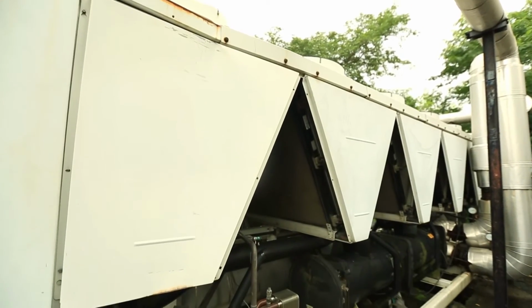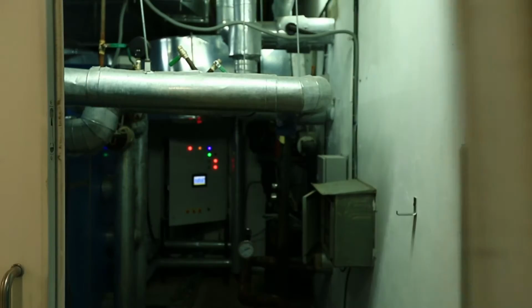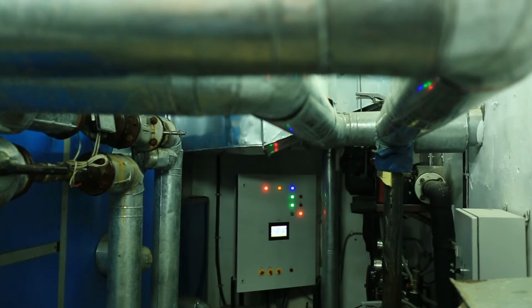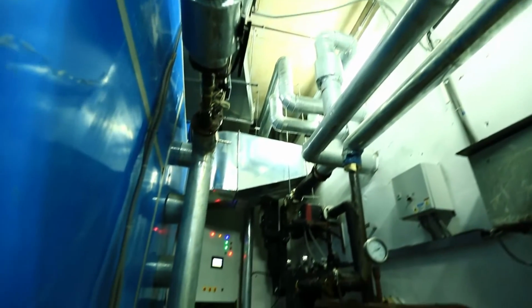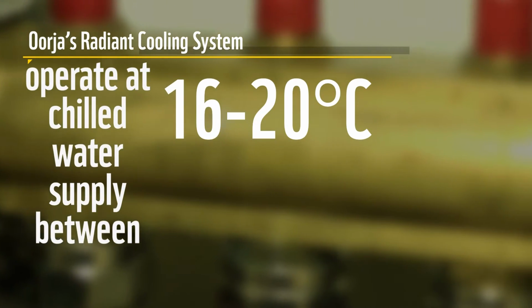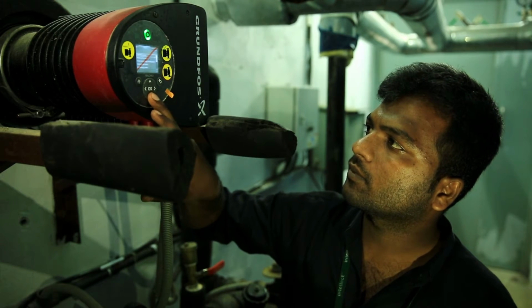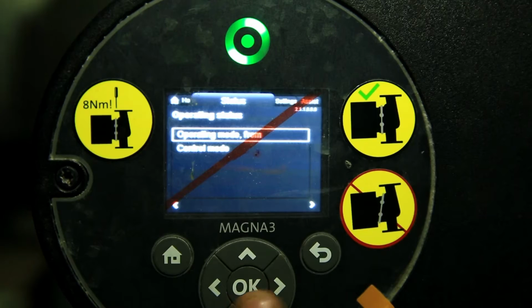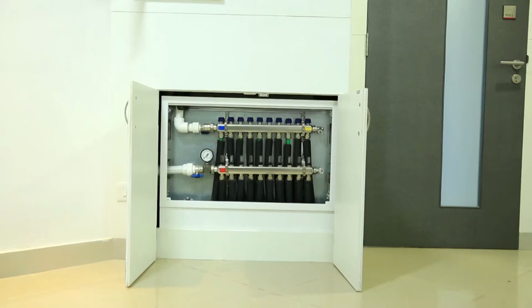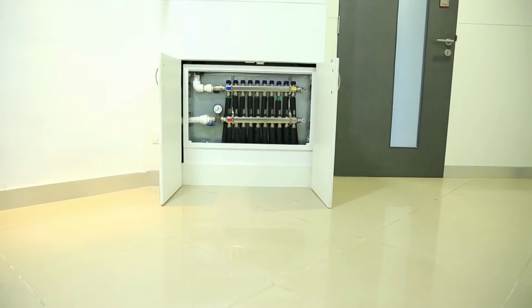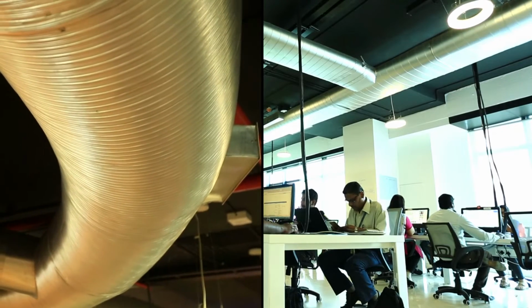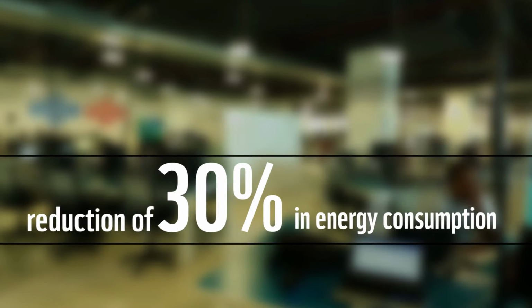Conventional centralized HVAC systems using chillers and AHUs require chilled water supply at 7 degrees Celsius, as compared to Oorja's radiant cooling system that can operate at chilled water supply between 16 to 20 degrees Celsius, leading to significant savings in the power consumed by the compressor, as the compressor has to work more to produce chilled water at 7 degrees Celsius. Furthermore, the solution does not require a high-powered motor to transport large volumes of air through the ducts, offering a reduction of 30% in energy consumption.